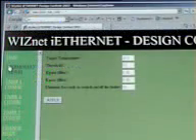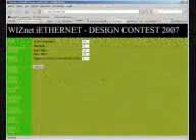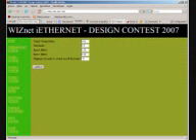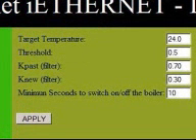The next page that you can see is thermostat config. We can change the principal thermostat parameters such as the target temperature. The threshold is the maximum difference between the ambient temperature and the target temperature without switching the boiler. The other parameters are the filter parameters that represent the importance of the past value and the new values. The sum of the two parameters must be 1. Here we have the minimum time from switch to switch in the system, so the boiler lasts longer.